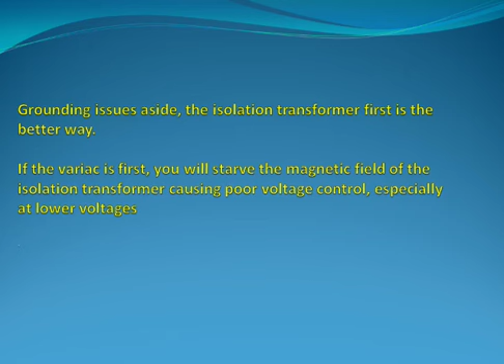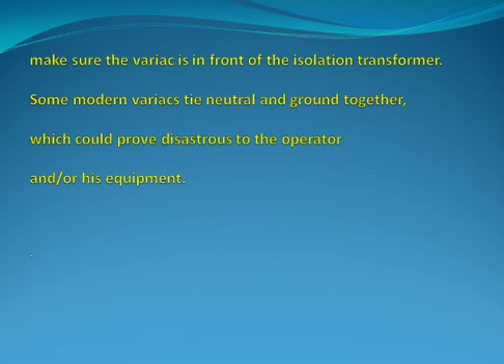Next: make sure the Variac is in front of the isolation transformer. Some modern Variacs tie neutral and ground together, which could prove disastrous to the operator and/or his equipment. Okay, I didn't know that, that they tie neutral and ground together in some Variacs. I know that happens in the transformer out in the street, and sometimes at the fuse box at your house, but okay, it was a new issue to me. Is it convincing me? I don't know, not really, but we'll see.